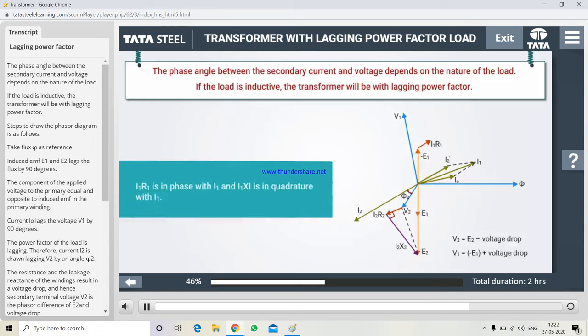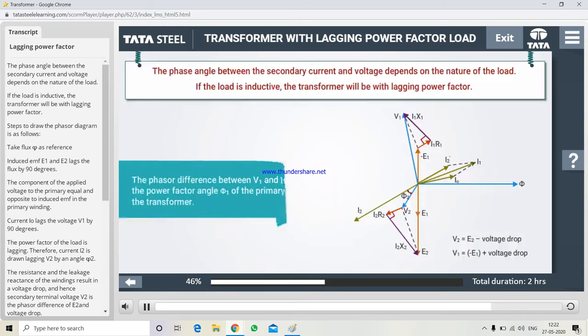I1R1 is in phase with I1 and I1X1 is in quadrature with I1. The phasor difference between V1 and I1 gives the power factor angle phi1 of the primary side of the transformer. The power factor of the secondary side depends upon the type of load connected to the transformer.